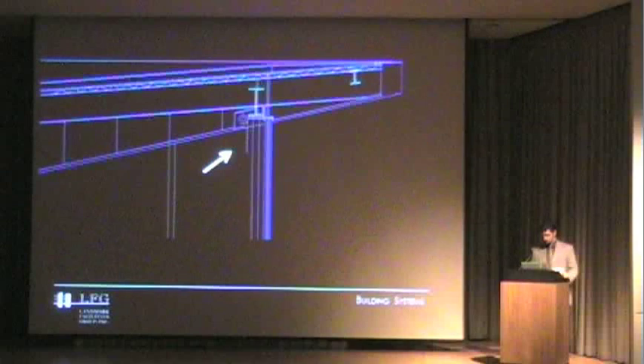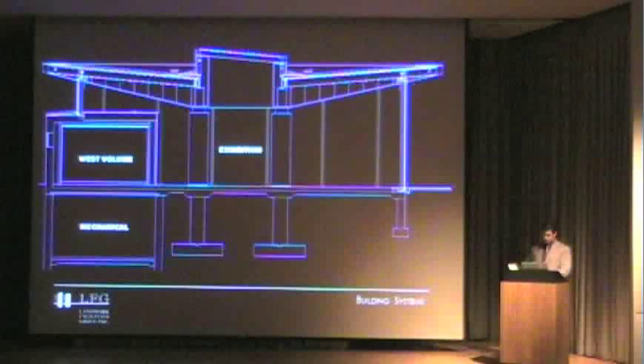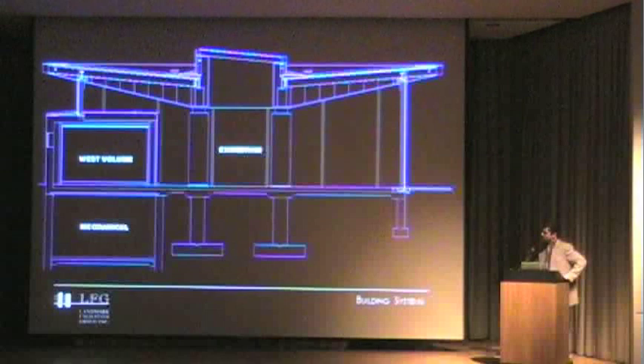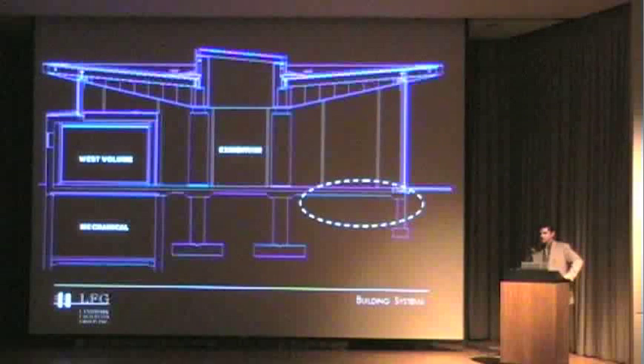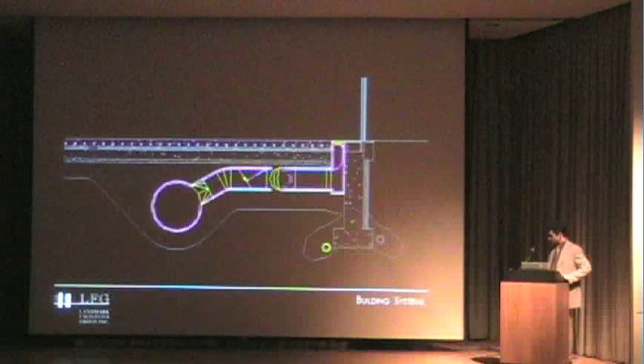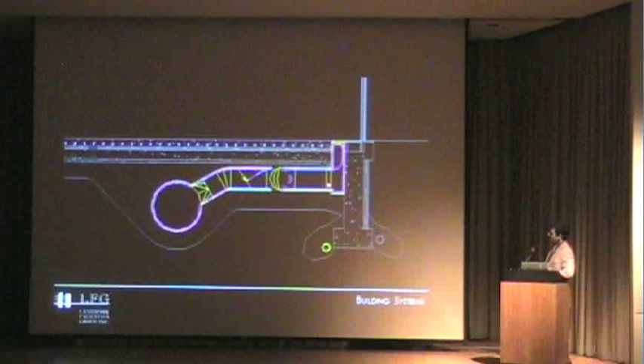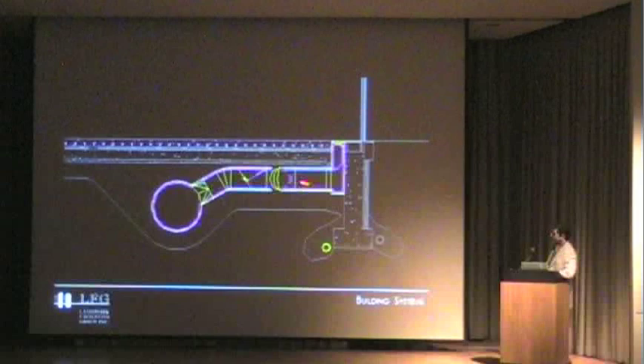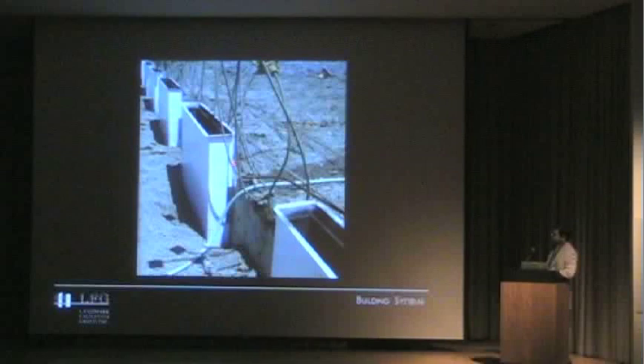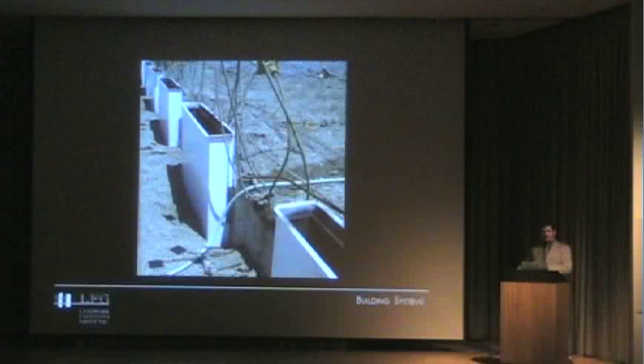In addition to dealing with these solar loads, we had a great deal of challenge with engineering acoustics. We focused our acoustic work and absorption on the ductwork below the floor slab. We started by slowing the air down at all of the air outlets, which surround the perimeter of the building with separate branch ducts. Each outlet is oversized, so the air moves very slowly through them under normal operating circumstances, and that low velocity helps reduce the outlet noise most people are accustomed to with an air system.